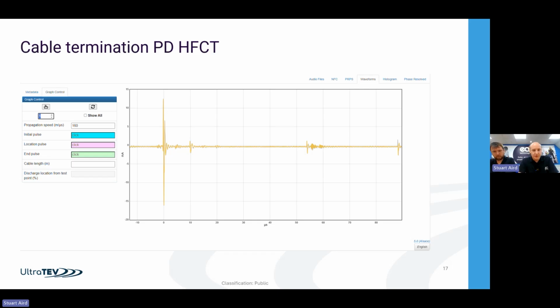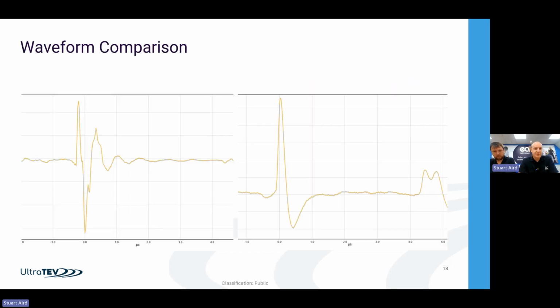So I've just got a comparison on the next slide that shows between the two. We can see in this one that the time between there is around about a quarter of a microsecond, whereas here we're talking over half a microsecond. So there's a big difference in the speed of the waveform. You get a lot more ringing in the waveform as well. So again, indicating that this activity is probably much more local to our termination. We're not seeing the reflections that we've seen in our previous one as well, showing an indication of multiple reflections along the cable, indicating a location along the cable route.